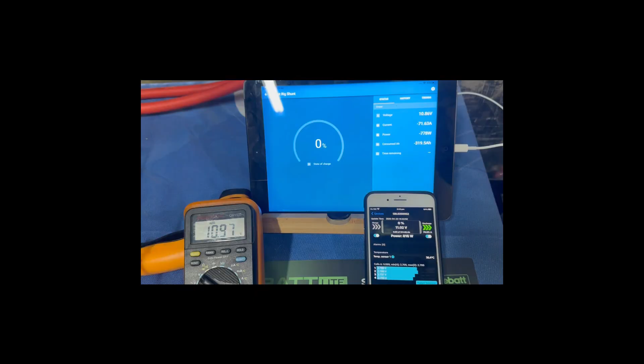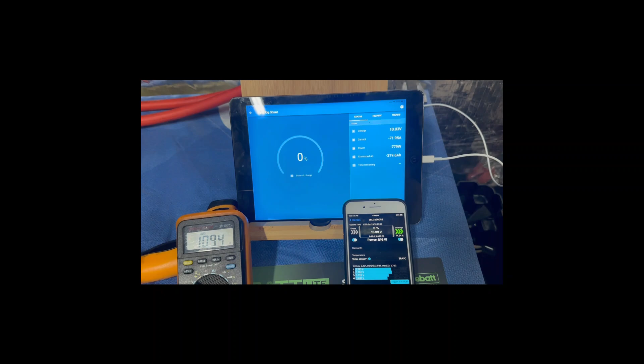There we go, low voltage has just come up on the inverter, so the inverter is going to cut before the BMS. Nothing I can do about that - I've set that inverter as low as it'll go for the voltage cutout.